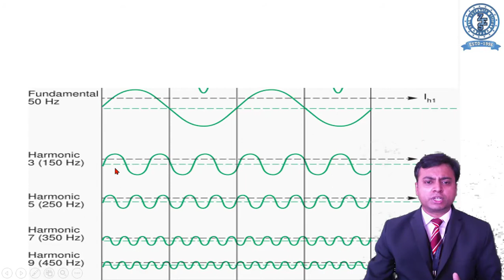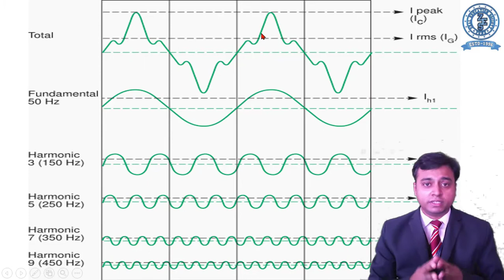Similarly, if you have 5 high points, that is 3 on the positive and 2 on the negative, over here you have fifth harmonic. Similarly, you have seventh, and similarly you have ninth. All these harmonics, if mixed together with a fundamental component, will distort the waveform, and that distorted waveform will look like this. Now this is not a sinusoidal waveform. This is not required. This is a waveform distortion, and this is how harmonics will be affecting the system.